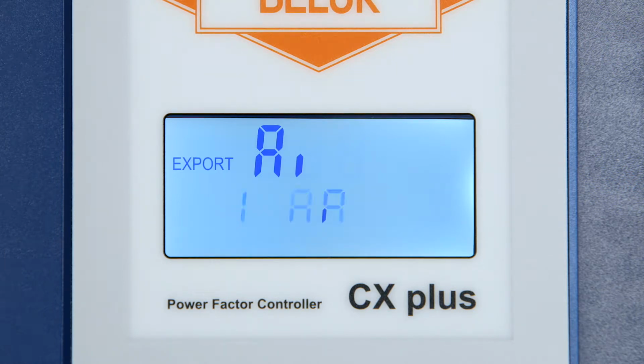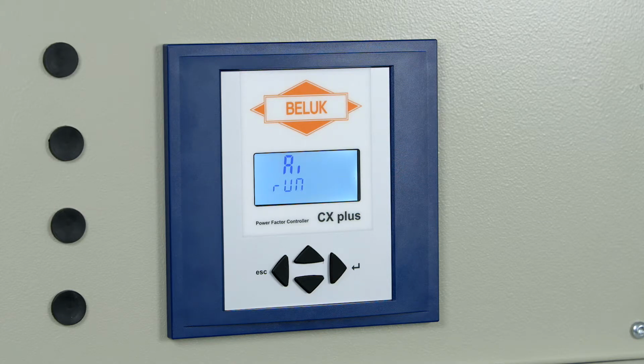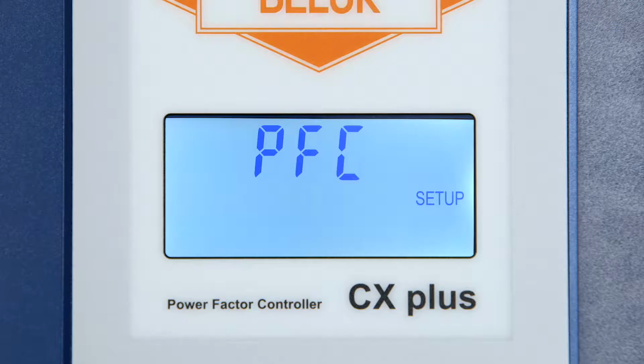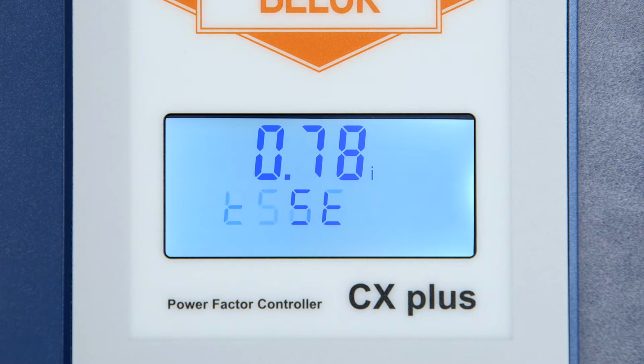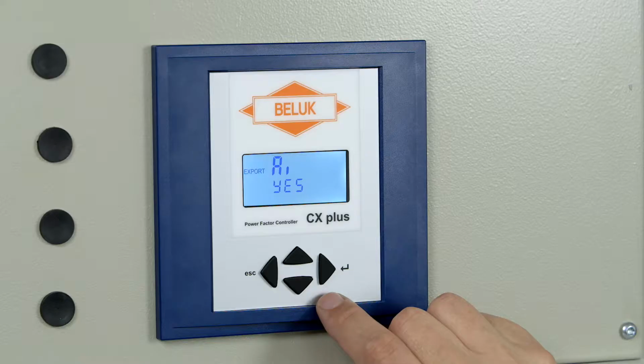After successful completion of the AI, the individual step types can be checked under the menu item Out and be adjusted if necessary. Finally, the Power Factor control is activated by confirming the menu item PFC on. Commissioning is now completed successfully. The CXplus shows the message First Setup OK in the display and the control can start.